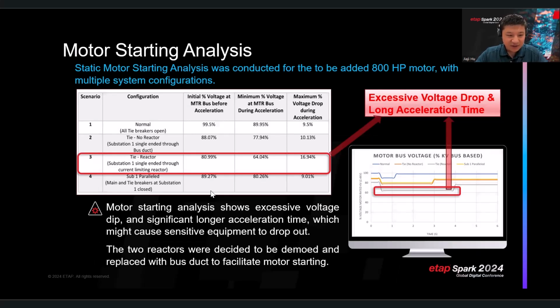But per their standard, this configuration should also be considered for the arc flash and the motor starting. And also, of course, we have the substation single end configuration, which is 2 and 3 here. When you have the tiebreaker closed, one of the main breaker closed, and the other one open. By engineering experience, we know that probably the single-ended substation give us the worst motor starting peak profile. So that's why we have a no reactor and the reactor case to compare how much voltage drop is actually brought in by the reactors.